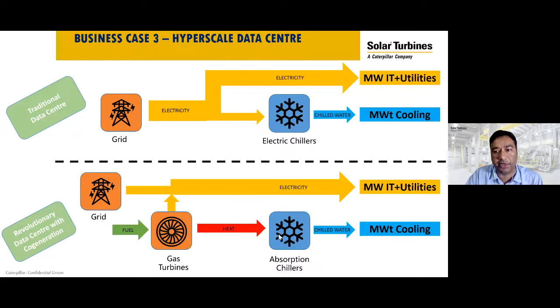This way, because of its high efficiency, we will reduce the PUE. The typical CHP efficiency you can consider around 80-90%. The payback will be around 4.5 years, and it's a reliable source of power with redundancy. The savings per year for customers will be around $9.5 million US, and there will be a lot of savings in terms of carbon emission, 160,000 tons we can save.